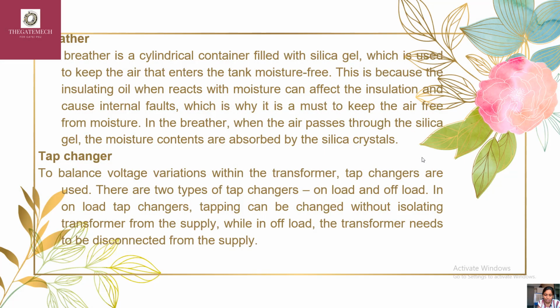Next one is the breather, filled with silica gel. The silica crystals used in silica gel absorb moisture, which keeps the air that enters the tank moisture free. This is because insulating oil, when it reacts with moisture, can affect the insulation and cause internal faults, which is why it is a must to keep the air dry. When the air passes through the silica gel, the moisture is absorbed by the silica crystals.